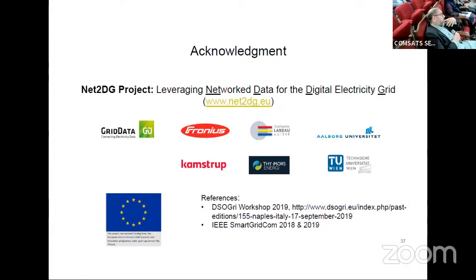Yes, I agree, in the UK and some US states they already have the system. But since this project was specifically for Germany, Denmark, and some places in Austria, they were lacking this kind of system - where fault location, field data collection, mimic board display, state estimation, and real-time power flow are all already running and decisions including contingency analysis are made from that data. So why shift away from that? What was the problem?